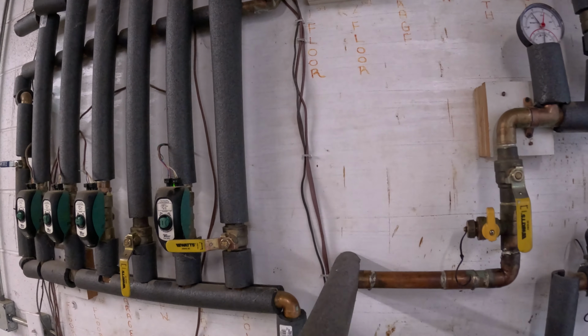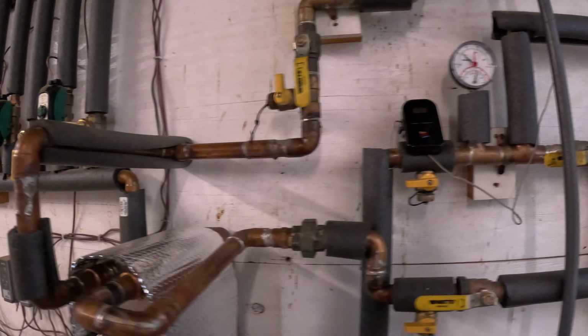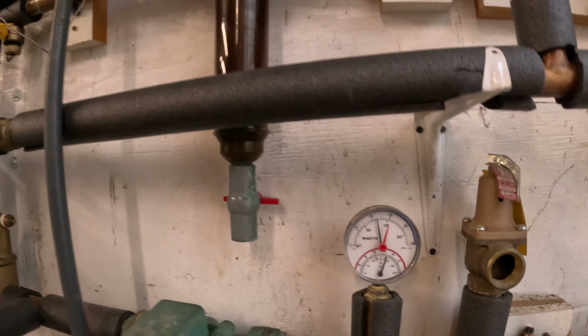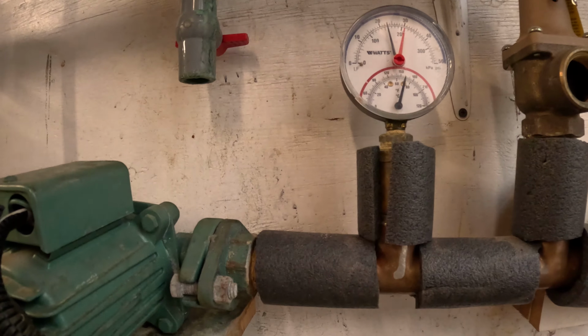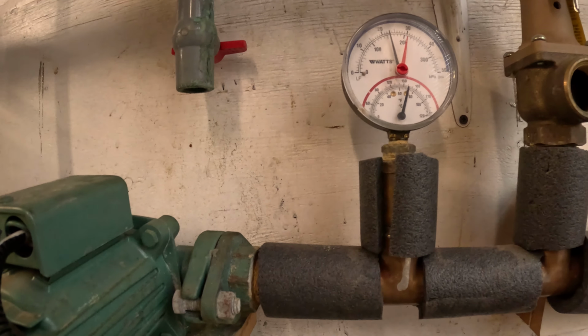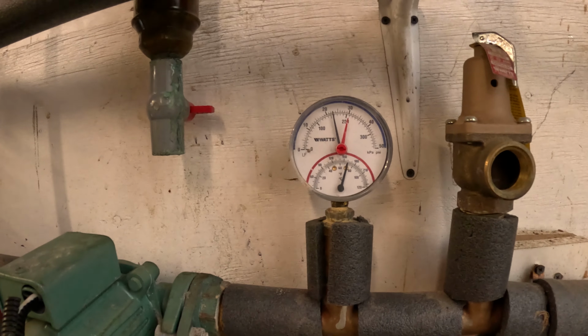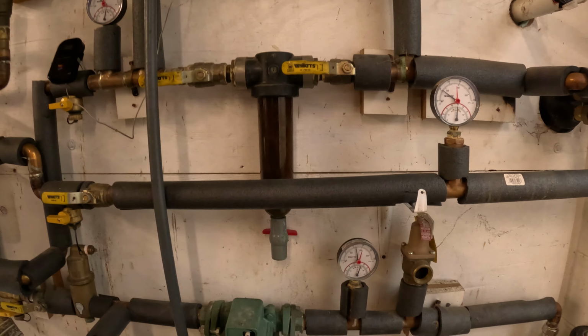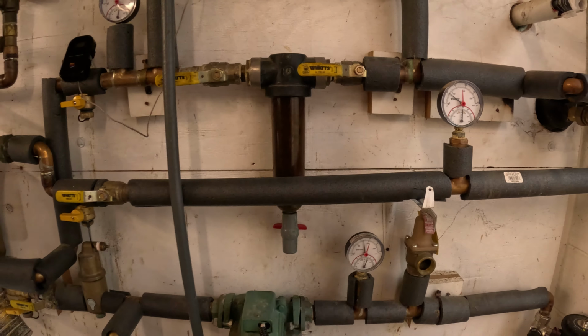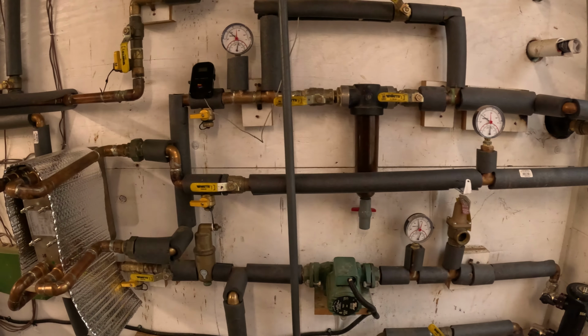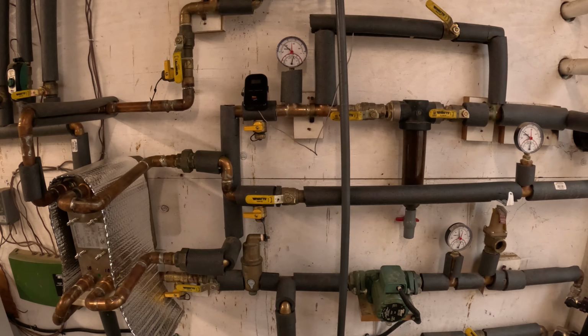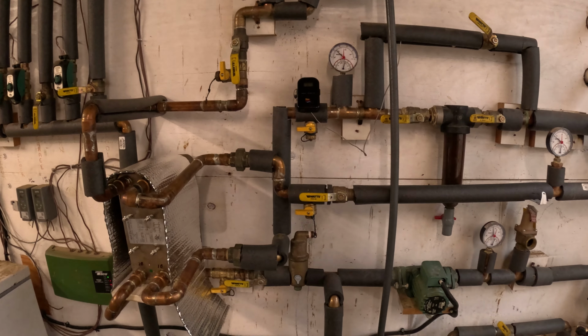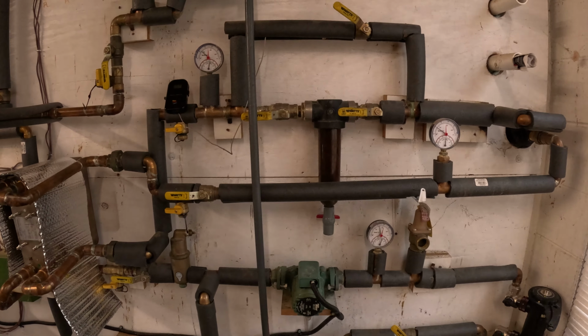It goes through the heat exchanger and comes out, and we're sitting at about 160, pretty close. So I mean, it's almost the same. That heat exchanger really does well, and we got close to 160 degree water temperature coming in from the boiler, and on the house side what's leaving is about 160 degrees.